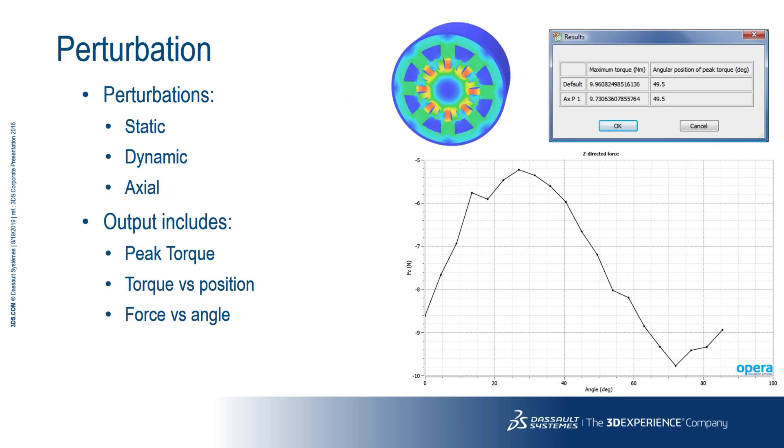The perturbation analysis is an extension to the torque v angle analysis for modelling various types of eccentricity, described as perturbations. The eccentricity can be static or dynamic radial or axial in 3D. The output includes the value of peak torque, its mechanical angular position and the torque versus position curve, but also the addition of the forces versus angle.